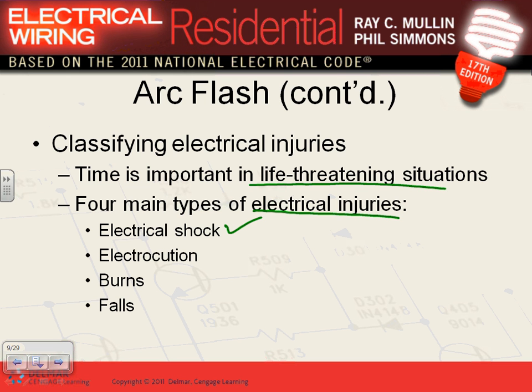The problem, guys, isn't the shock as much as electrocution. That happens when you grab a grounded object, a piece of panel, and then grab a hot object with your other hand. Now you act literally as a lamp or a motor. You can't let go, and the current keeps cooking you, circulating through your body. The circuit breaker thinks you're a sump pump or a refrigerator being fed, so it doesn't trip.